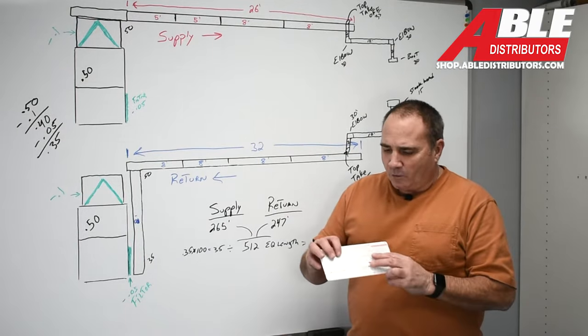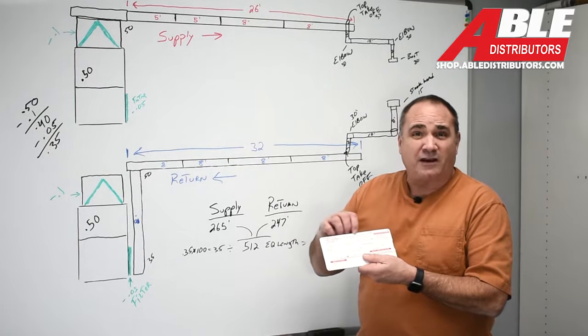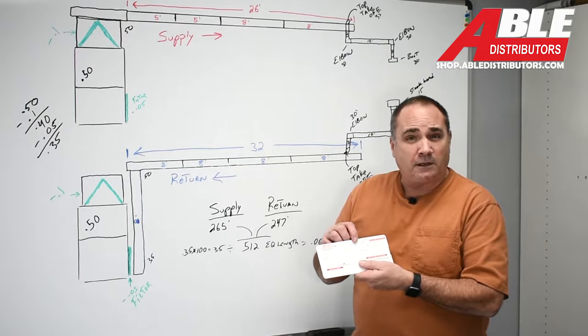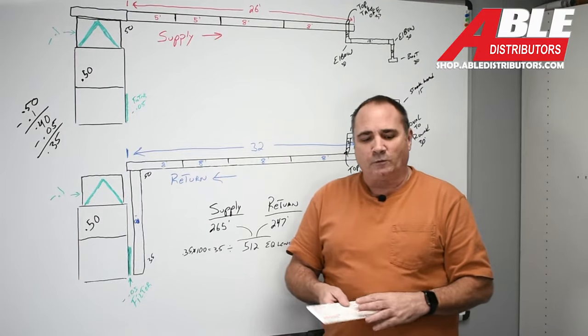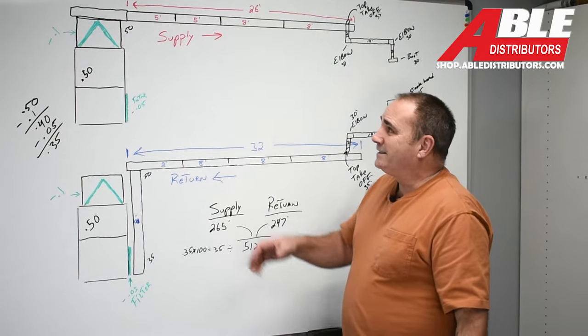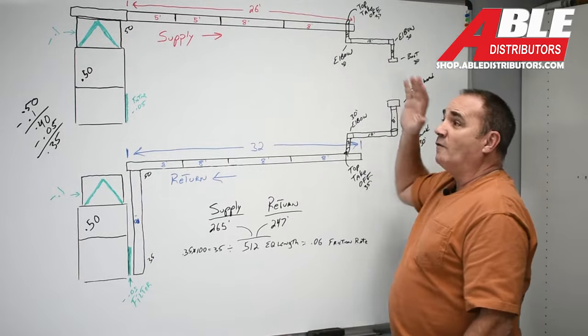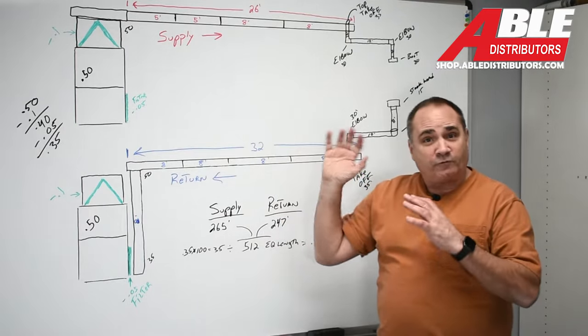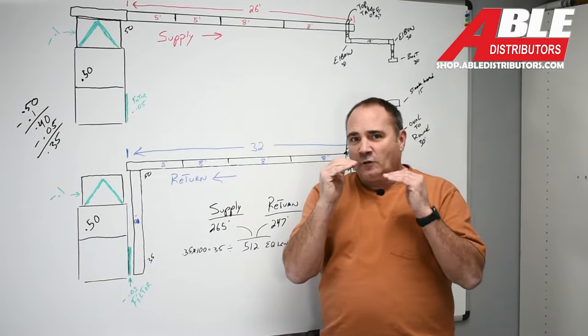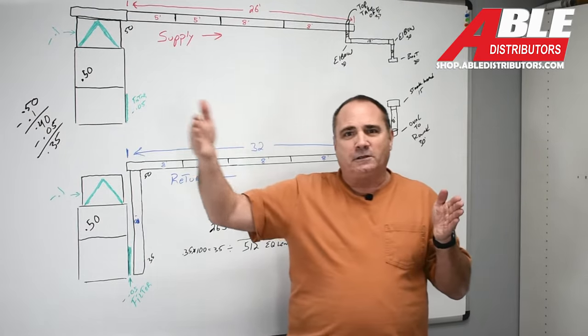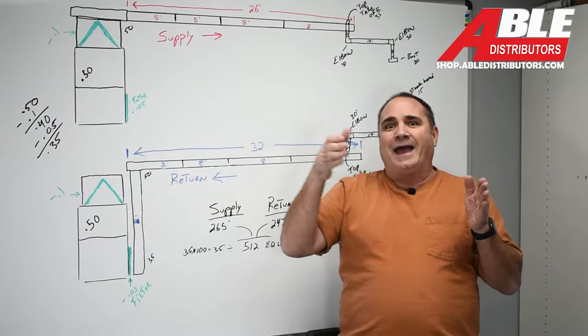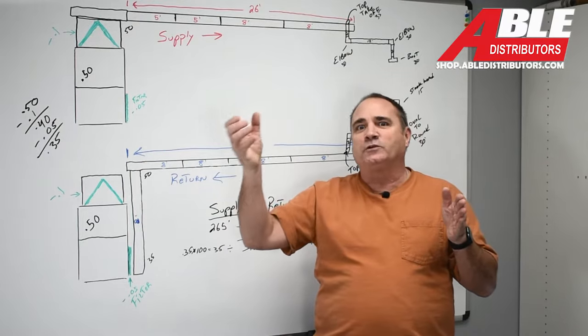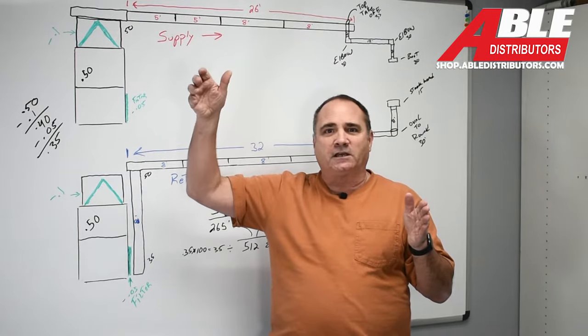But to get what friction rate you're actually going to want to use on your ductulator, there's a little bit of a math problem and a little bit of a layout problem. So what you need to do is get the equivalent length of the longest run, both for supply and return. Now that longest run might not necessarily be the one farthest from the furnace. There might be one ahead of that one that has more turns and twists, goes up to the second floor.